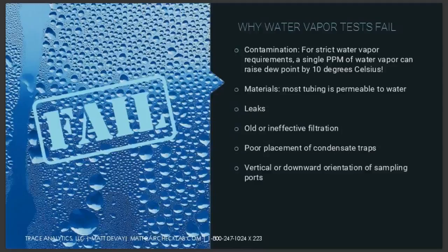Materials, these can lead to contamination as well. If you're using polymer tubing and you need to try to hit a stricter dew point, you're going to have some pretty bad luck with that. Most tubing is permeable to water. There's not a polymer out there that is completely impervious to water. Even PTFE has a fairly high rate of permeability to water. And I say high rate, it's in the parts per million kind of range, but as you can see, a single part per million makes a big difference with this.